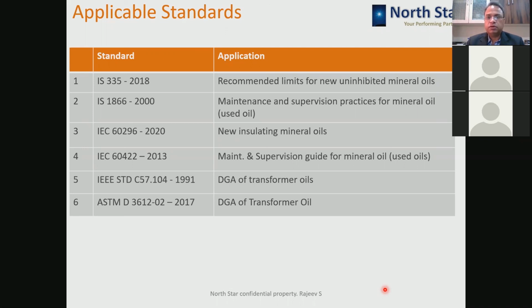When you use the oil in the transformer and you wish to test that oil which is inside the transformer, then IS 335 will no longer be applicable. It will be IS 1866:2000, which is about maintenance and supervision practices for mineral oil. Then IEC 60296 is there, which is for new insulating mineral oils, and IS 335 is based on IEC 60296.